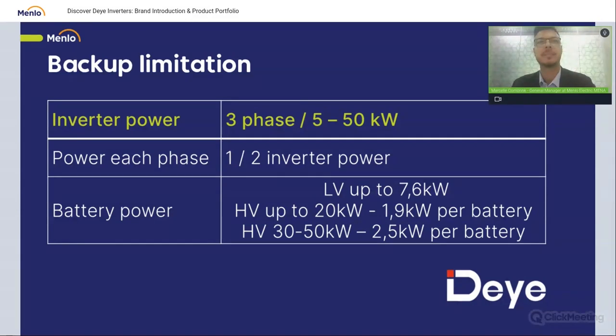Backup limitations. There are basically three areas that we look at: inverter power, power for each phase, and battery power. On the inverter side, inverter power is three phase and it's 5 to 50 kilowatt. There are no solutions higher than 50 kilowatt. Power per phase is half of what the inverter power is.